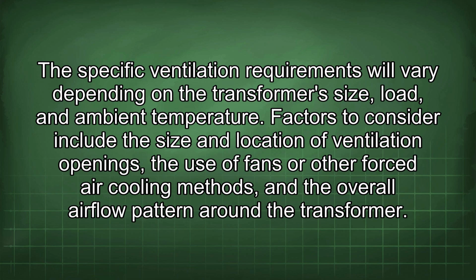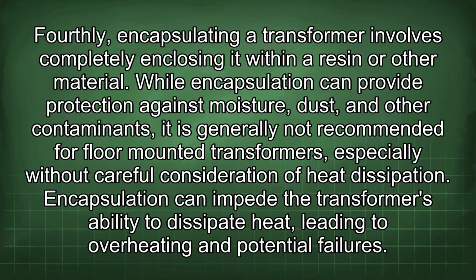The specific ventilation requirements will vary depending on the transformer's size, load, and ambient temperature. Factors to consider include the size and location of ventilation openings, the use of fans or other forced air cooling methods, and the overall airflow pattern around the transformer. Fourthly, encapsulating a transformer involves completely enclosing it within a resin or other material.